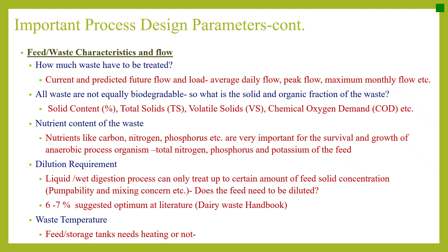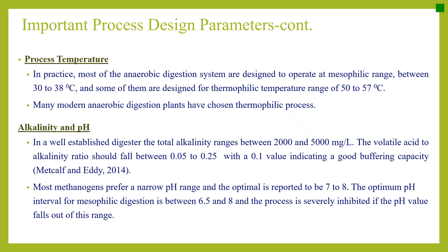Waste temperature is also important — feeds like FOG tend to solidify at colder temperatures, so feed or storage tanks need to be heated to keep the feed in a liquid state. We also need to know the incoming waste temperatures because we have to raise them to the process temperature. In practice, most anaerobic digestion systems are designed to operate at the mesophilic range of 30 to 38 degrees Celsius.